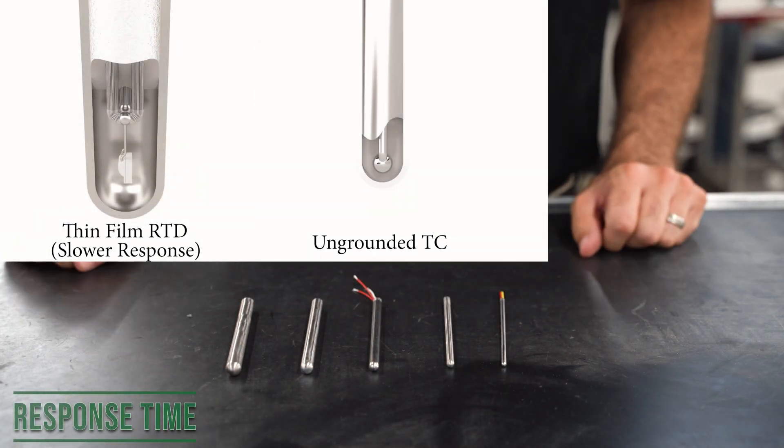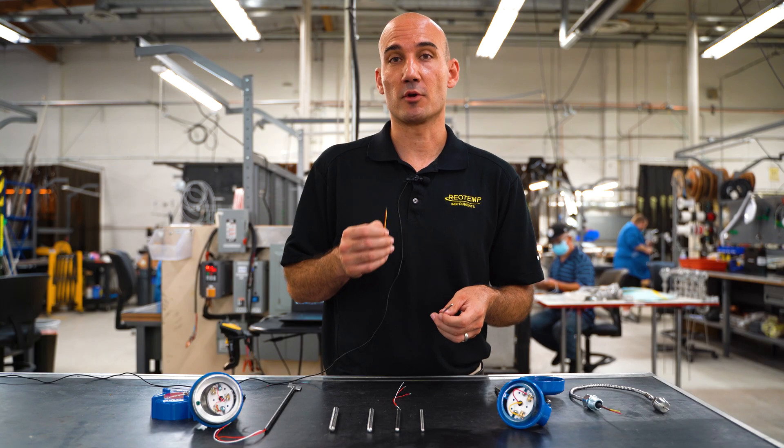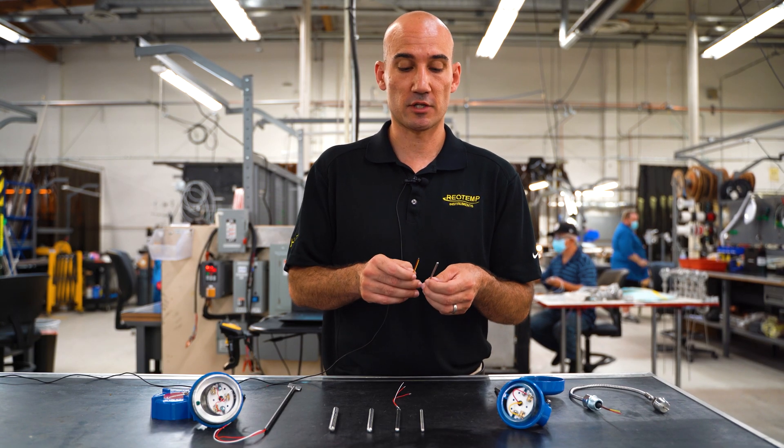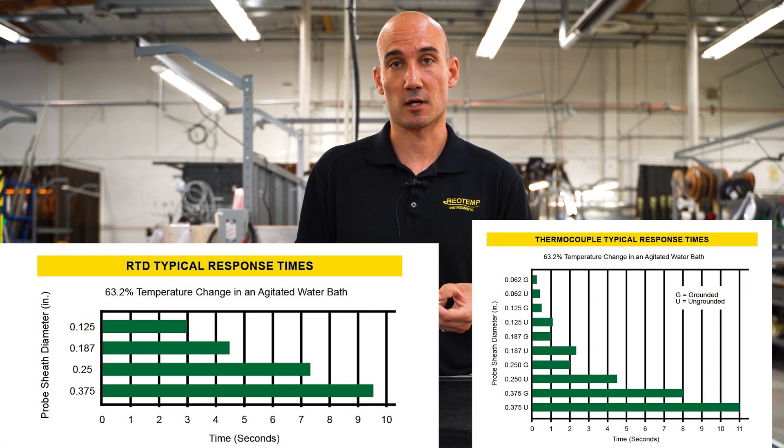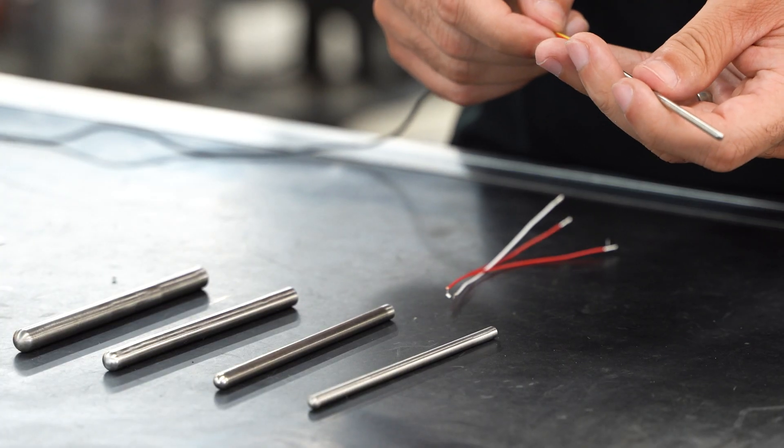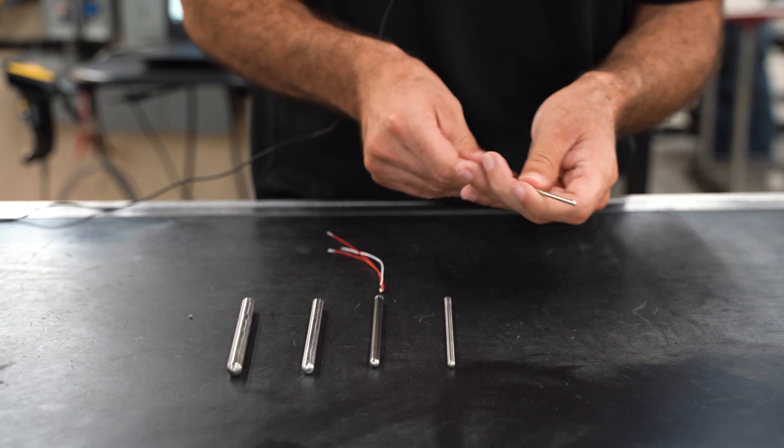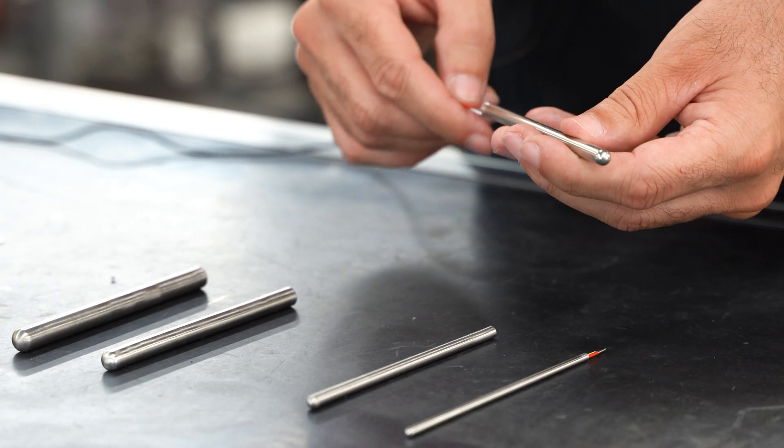RTDs cannot be grounded, which gives them a slower response time than a grounded thermocouple. Also, a thermocouple can fit inside of a smaller sheath diameter, and that smaller sheath diameter will give you a reduced response time. For example, a grounded thermocouple inside of a 1/16th stem diameter is going to have a faster response time than an RTD inside of a 1/16th diameter stem.